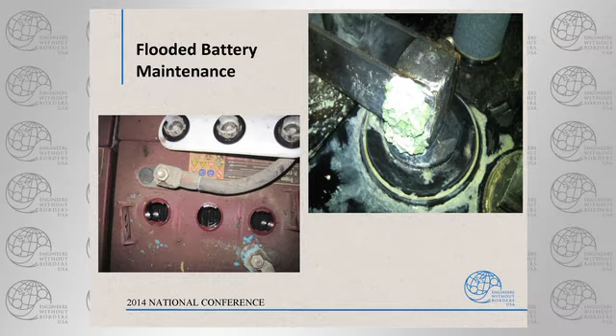Be cautious. A lot of times this hydrometer gets hung up back in the room where the battery is. Some of them will put a little glass test tube or something down here to catch what drips out later. Well, what drips out later is battery electrolyte, sulfuric acid. Water will evaporate until that is extremely concentrated. So what drips out sits in a little jar, a little more water evaporates out of it just from vapor pressure, and you get really concentrated acid.